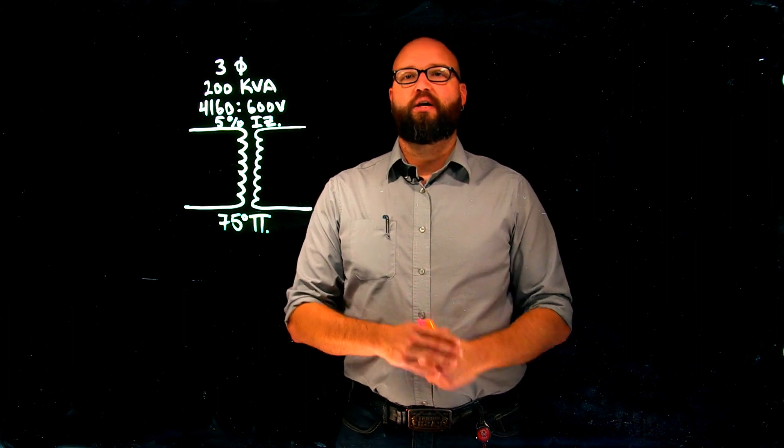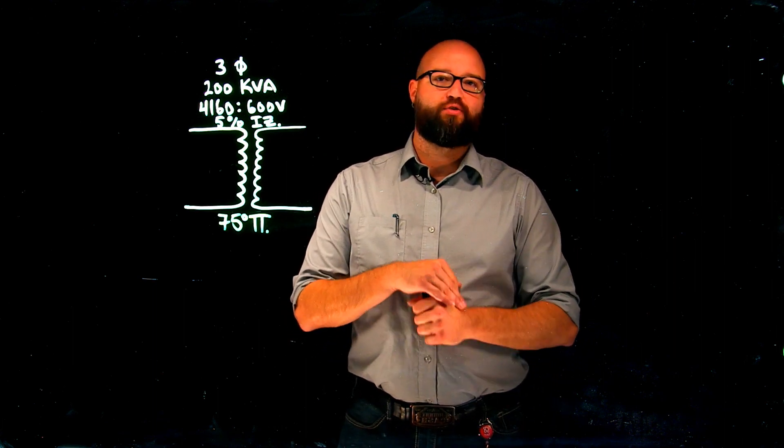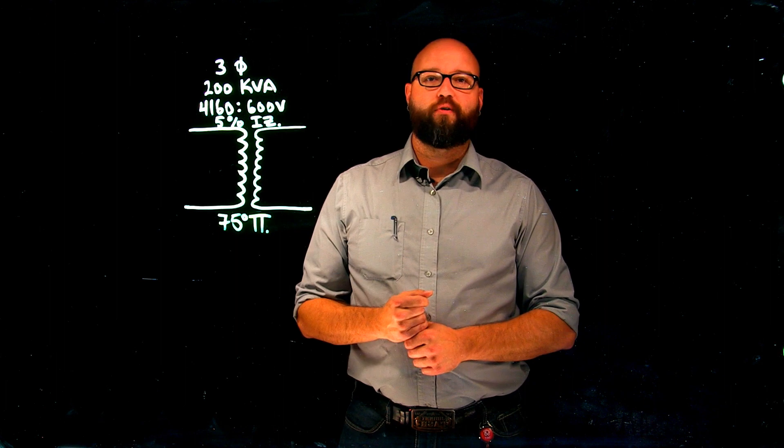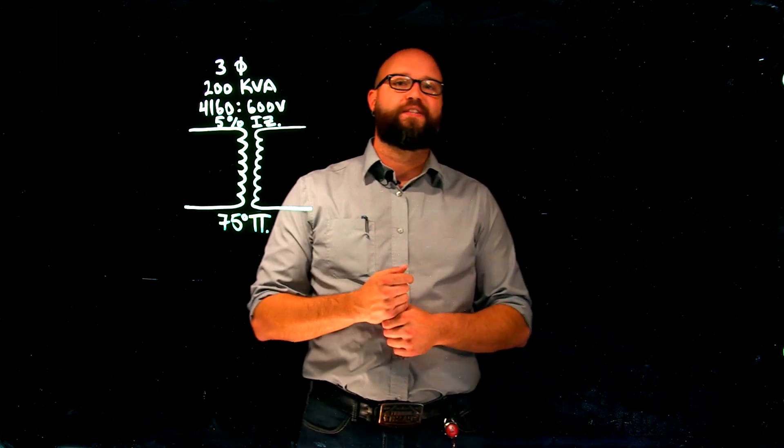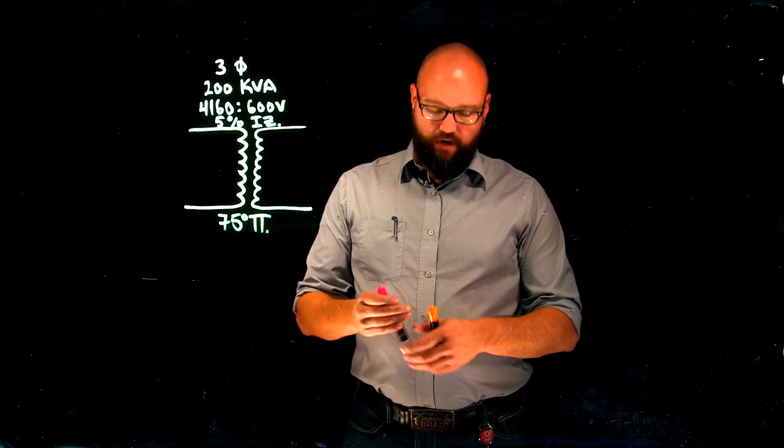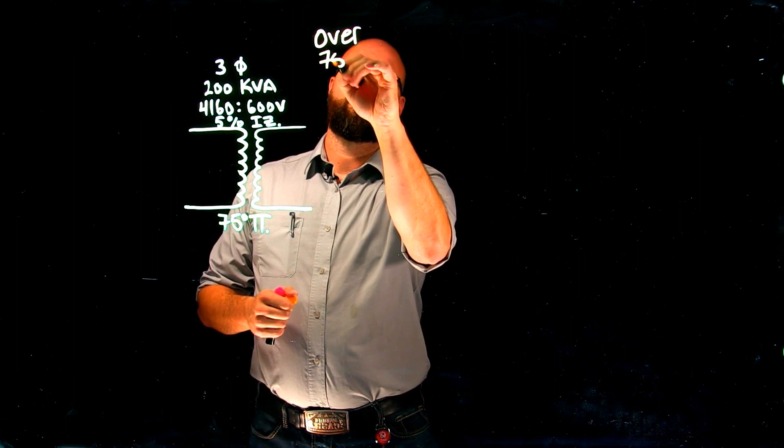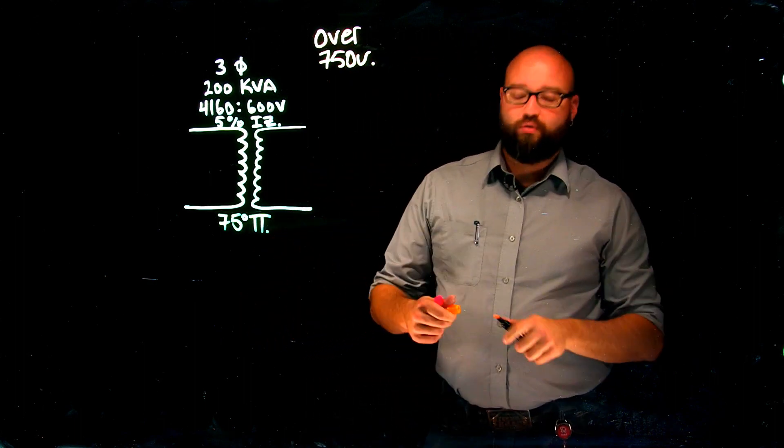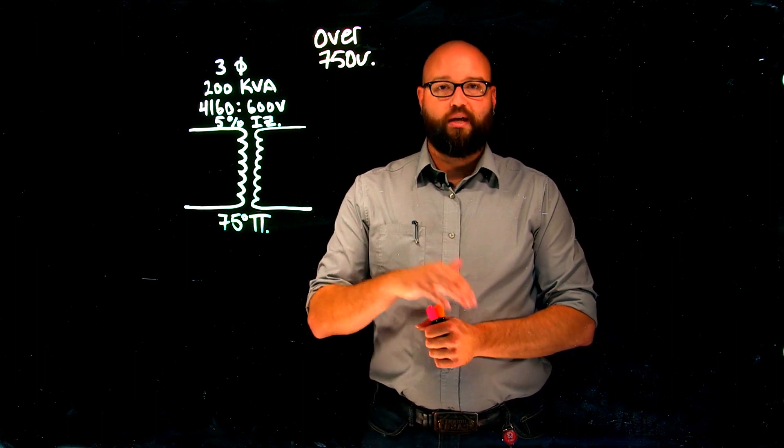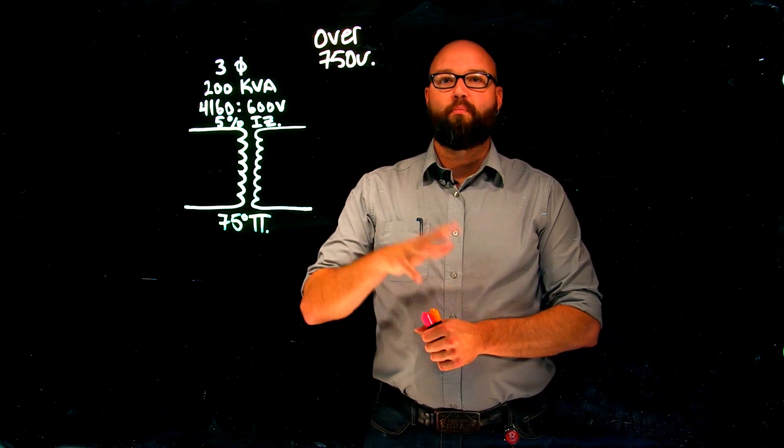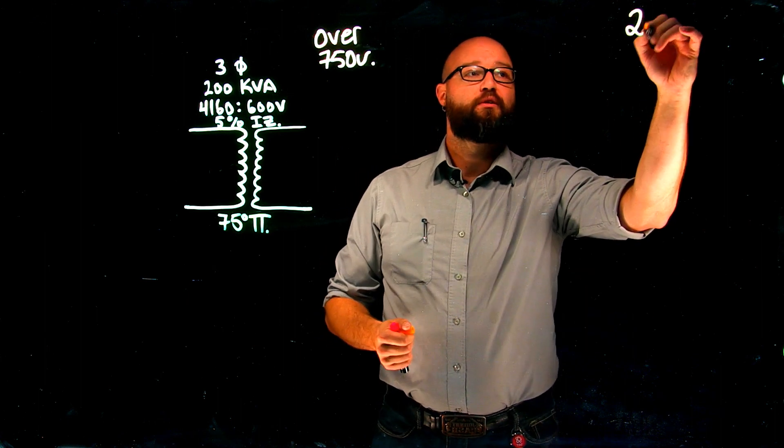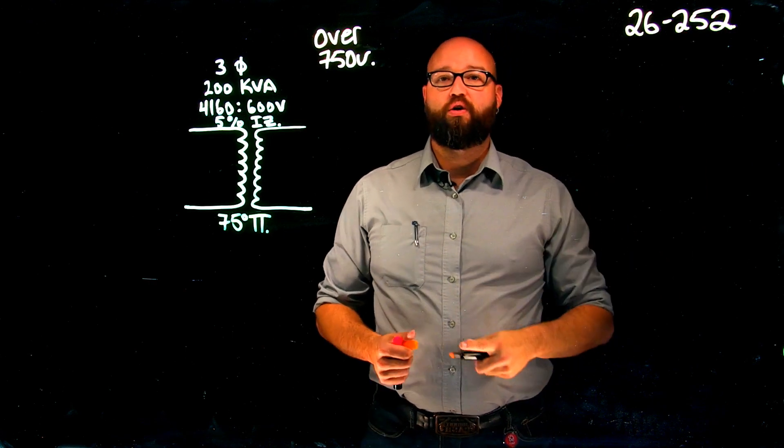In this series of videos, we are going to take a look at determining overcurrent devices for different transformer installations. This will be a four-part series that covers all the general rules for calculating transformer overcurrent devices in the 23rd edition of the 2015 Canadian Electrical Code. The first that we're going to start with here is our over 750 volt transformer on the primary. This does not matter whether it's a dry type or liquid filled. This applies to both. So anything over 750 volts, we're going to be dealing with 26-252 as our code rule for reference.